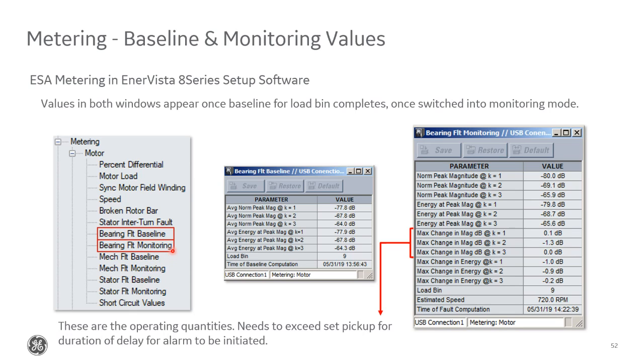If we open these up, in this example, we're going to open the bearing fault values. You can see for the baseline what the average peak magnitude values were, again, including up to the third harmonic. You can see what the average normal peak magnitude values are. And then you can also see what those average energy values were, again, as a double checking mechanism.